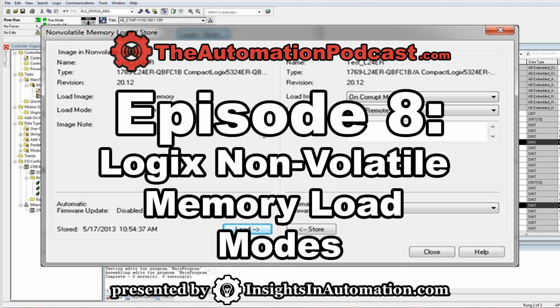All right, now if everything's going well there, we're ready to try our final test. This test would test loading non-volatile memory when the processor's memory is corrupt. Now I want to point out that the processor having a default program is not the same as the processor having corrupt memory.